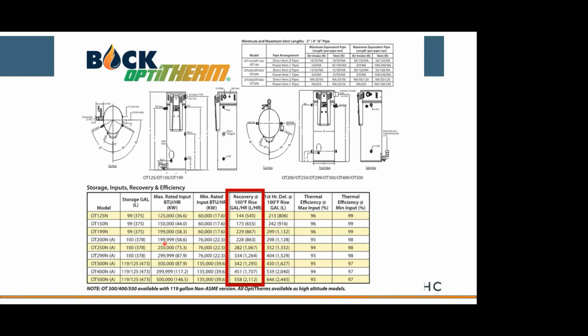So you'll see a lot of manufacturers get their burners right up to 199, so it can be non-code. And as soon as you get to 200, you need to be ASME code. Okay. Why one versus another? You would think safety-wise in a building, you're going to want ASME code. You have some owners that want to utilize non-code water heaters. An advantage for an owner, you don't have to pull a permit to pull or replace it. You also don't have to hire a union plumber to work on it. So you can have facilities work on a non-code water heater where that's not necessarily true if it's ASME. Okay. And I'll get to an example here towards the end. We'll beat that one up a little harder.